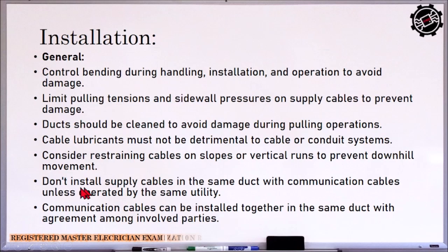Do not install supply cables in the same duct with communication cables unless operated by the same utility. So hindi pwede install yung supply cables in the same ducting as communication cables. Katulad pa rin yan doon sa ating conduit. If our communication cables are nakadaan sa conduit, hindi pwedeng same conduit pareho yung supply cable at communication cable. Communication cables can be installed together in the same duct with agreement among involved parties. So pwede siya, the exception, katulad din sa conduit. The exception is if the communication company and the utility company, yung may-ari ng supply cable, are in agreement na pwede at the same ducting or the same raceway or the same conduit ang kanilang dalawang klase ng cables.